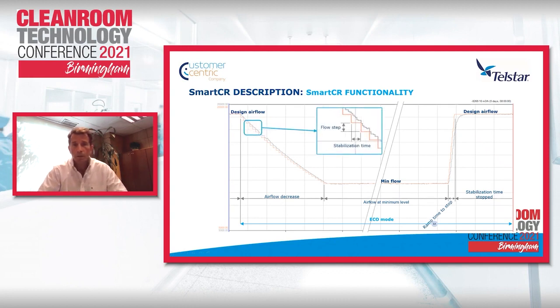As I have already explained, one of the most difficult parts of this is how we are going to qualify it. For that, we used an approach of sequential steps, where we have two parameters. One of them is the flow step, and the other one is the stabilization time. We determine a flow step equal for every step. This is the percentage of fan speed that we reduce. And the stabilization time is the time we assure that all the parameters are under control.